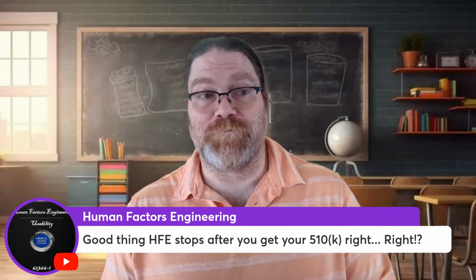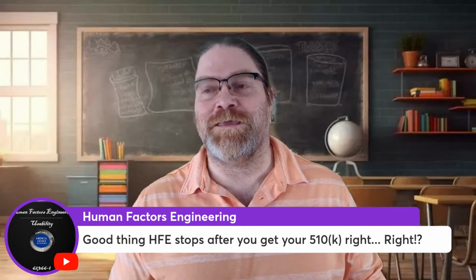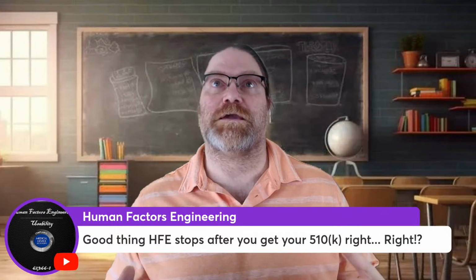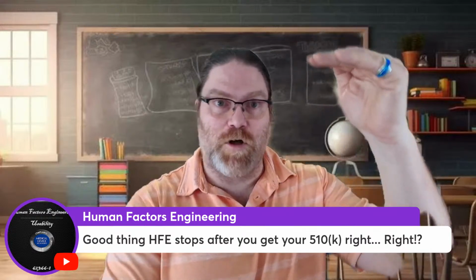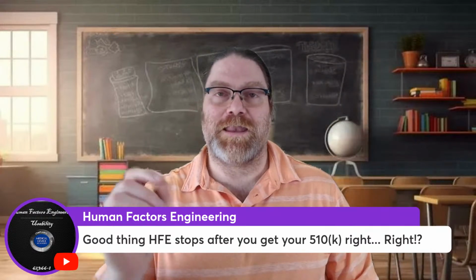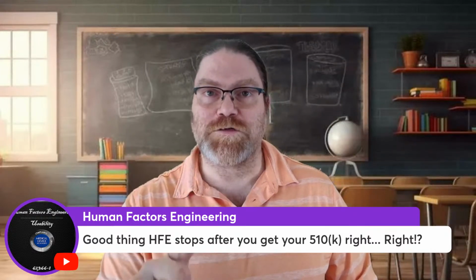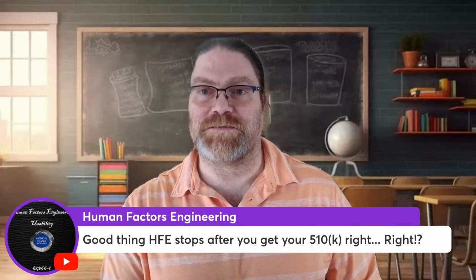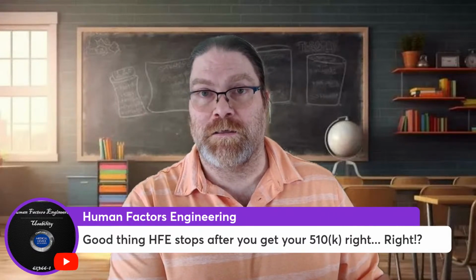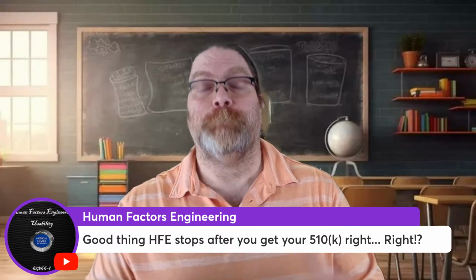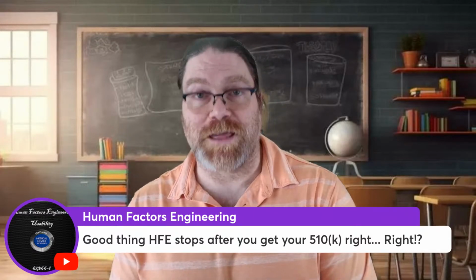One of my favorite videos is the last one we did on how to write a report. You have an 8-section report. The FDA tells you that you've got to have all these 8 sections. The last section is where the data from your summative testing goes. The first 7 are boilerplate from your previous work that you've done. So you could actually write 7/8 of your report before you actually start the study.